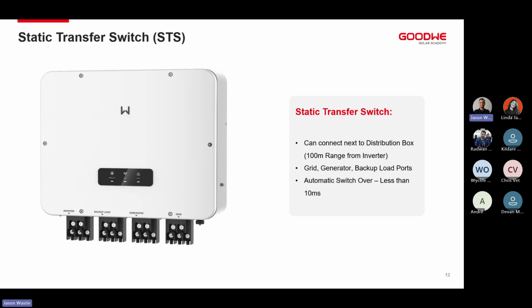Thirdly, this is where all of your AC transfers happen, or AC switchovers happen. You'll see at the bottom of the STS, there are 4 ports: an inverter port, backup port, generator port, and grid port. Meaning this is where your actual switching happens on the inverter or through the inverter on the AC side.